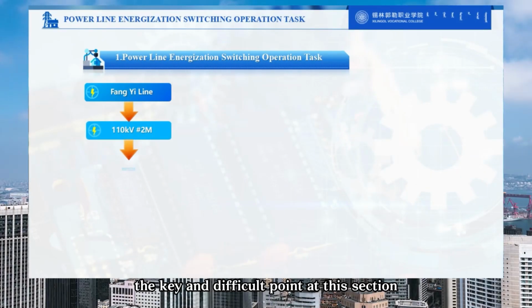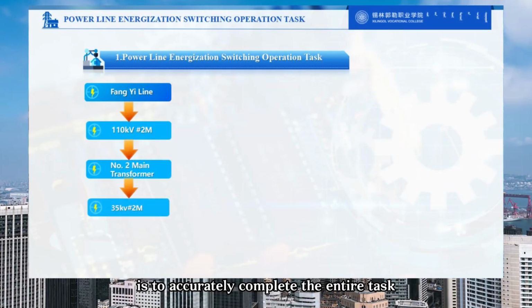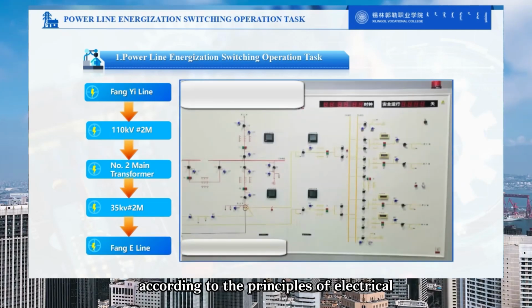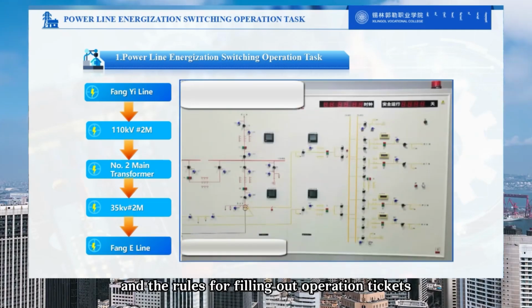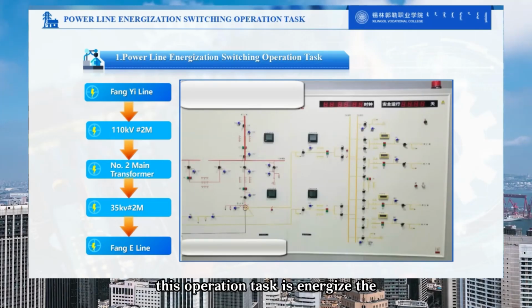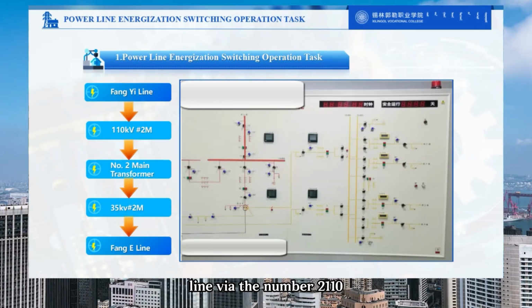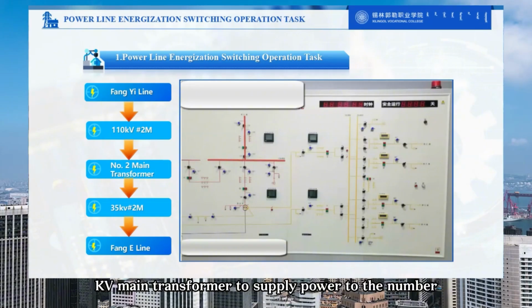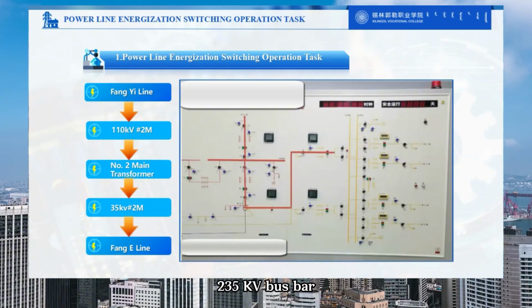The key and difficult point of this section is to accurately complete the entire task according to the principles of electrical switching procedures and the rules for filling out operation tickets. This operation task is to energize the Fang Yi Line via the number 2 110 kV main transformer to supply power to the number 2 35 kV bus bar, and finally energize the Fang E Line.